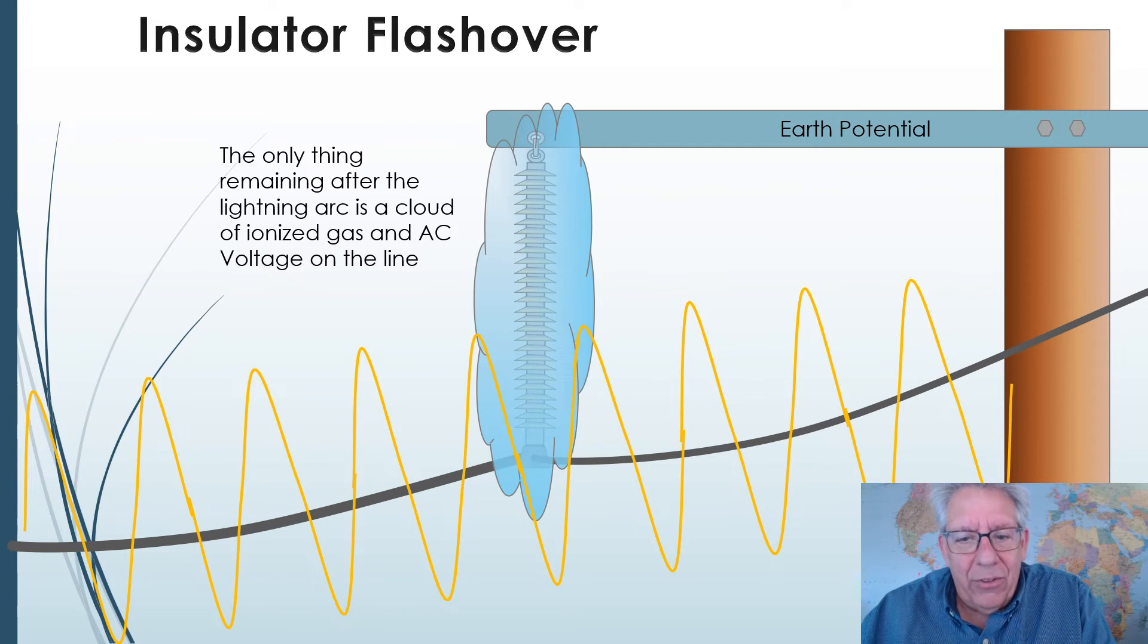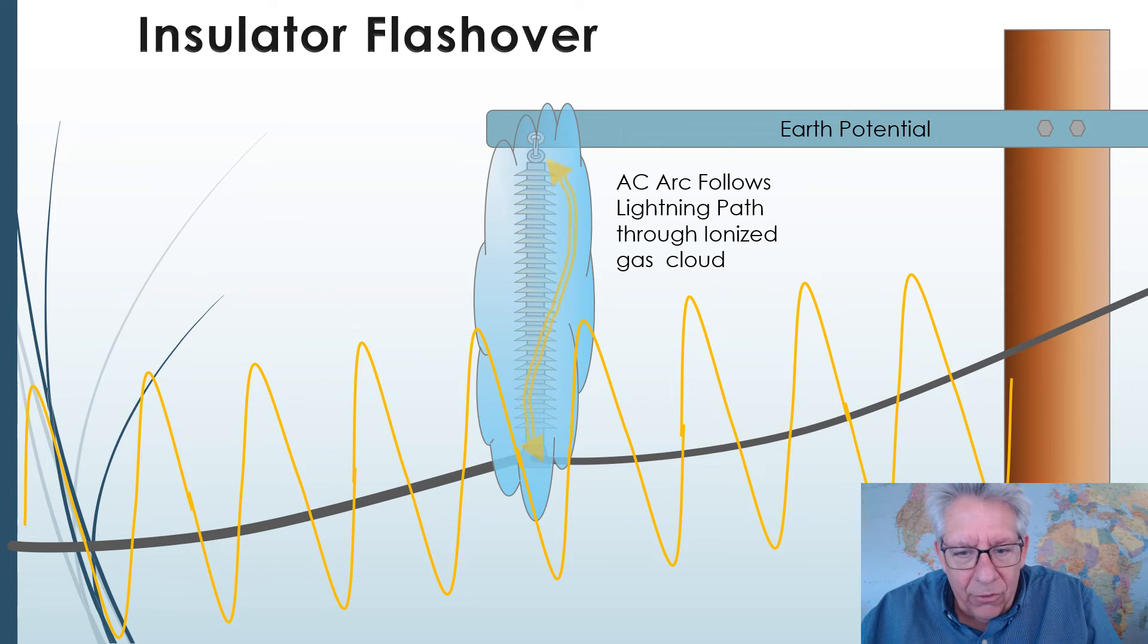Well, the AC voltage is still on the system. And what happens is that when it starts to reach peak voltage, it senses this high conductivity air around the insulator, and then it flashes over also. So the lightning flash is already completely gone, and then the AC follows it.